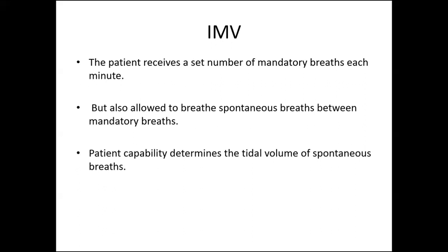In mandatory breaths, the patient will be supported by the ventilator, so he can get the desired tidal volume. But in a spontaneous breath, the tidal volume will be determined by the patient effort only. It will not be supported by your ventilator. But in certain modes, you can support them also. We'll see what other modes we can have. So you can support it by adding pressure support.